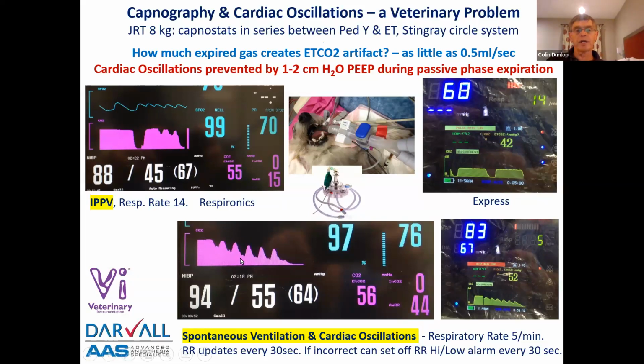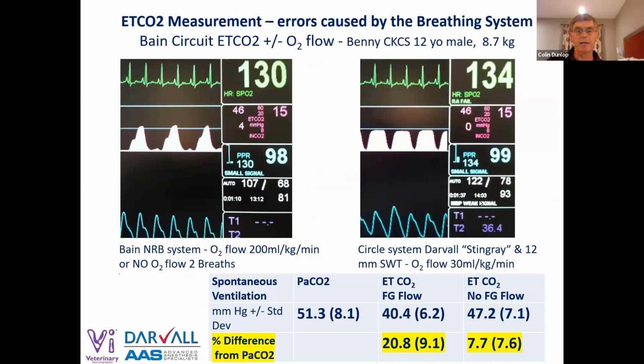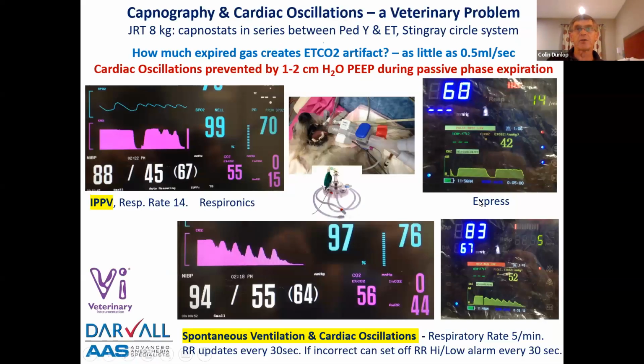You don't see these things with ventilators generally, because ventilators have a pressure relief valve in them that doesn't open generally till 2 centimeters of water. And that 2 centimeters of water is enough to stop those little puffs of gas. And those little puffs of gas, we're talking 0.5 mil per breath. We're not talking liters of CO2 here.